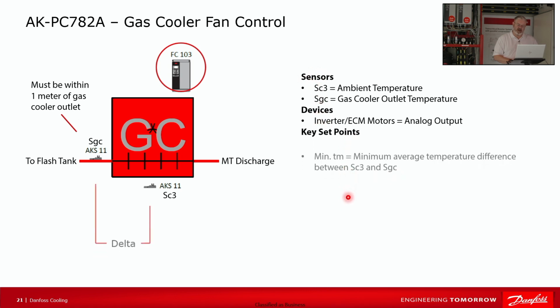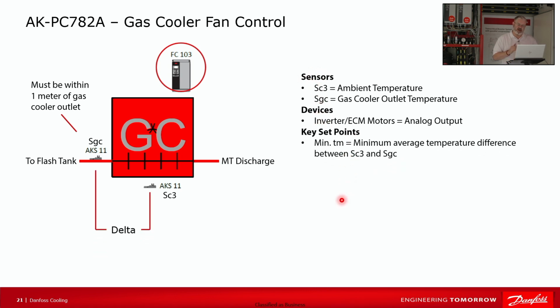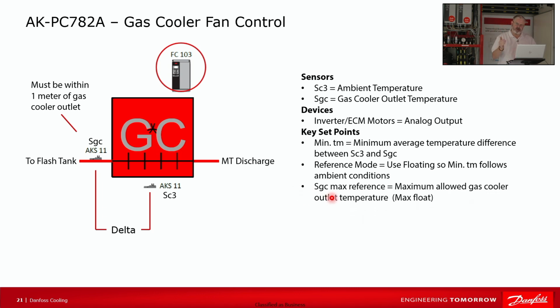The control strategy is pretty basic. We call it minimum TM, minimum temperature difference, but it's really just a delta between the ambient temp, which is the air coming into the gas cooler, and then the gas cooler exiting temp. We use a floating reference mode so that basically, as the ambient rises and falls, our 5 degrees difference just rises and falls with it. It's very similar to what's been done in the past with TD control.